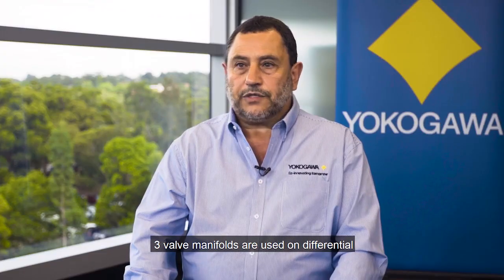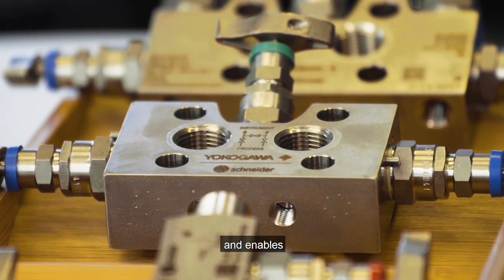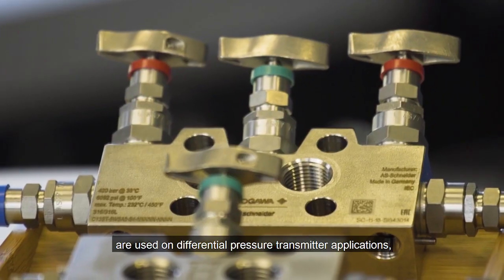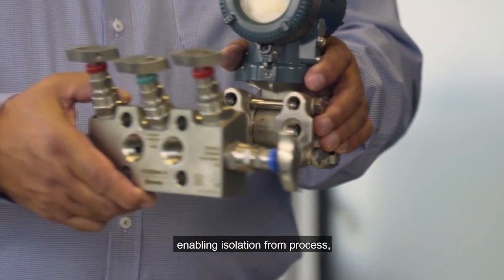3-valve manifolds are used on differential pressure transmitter applications that require isolation from process and enables equalising pressure across the pressure sensors.